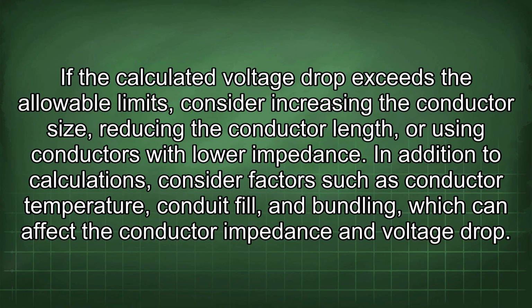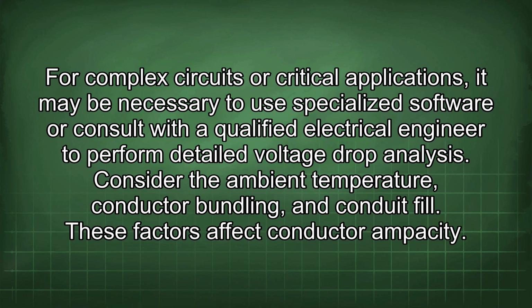If the calculated voltage drop exceeds the allowable limits, consider increasing the conductor size, reducing the conductor length, or using conductors with lower impedance. In addition to calculations, consider factors such as conductor temperature, conduit fill, and bundling, which can affect the conductor impedance and voltage drop. For complex circuits or critical applications, it may be necessary to use specialized software or consult with a qualified electrical engineer to perform detailed voltage drop analysis.